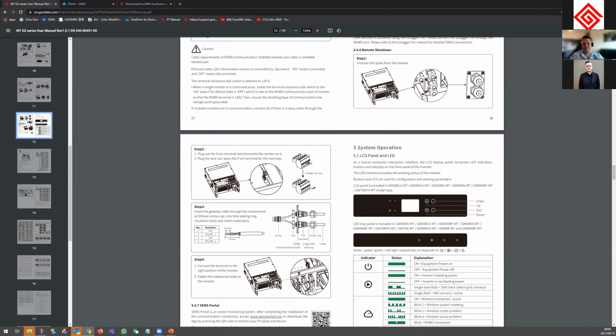Always make sure that this is inserted. Very often you might find this in your accessory box and not installed on the inverter already. So always make sure you take that out of your accessory box and install it in the inverter with a bridge on these 2 ports here. You'll see where the top 2 screws are. That takes the bridge to make sure that your remote disconnect function is disabled.